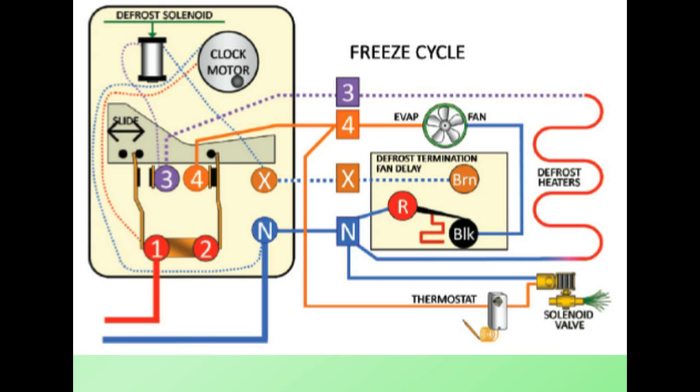There are a few different things to remember. Now, one thing before we start: this is our defrost termination and fan delay, and this is a schematic diagram here. This indicates a device that opens on temperature rise, which means it will close on temperature fall.